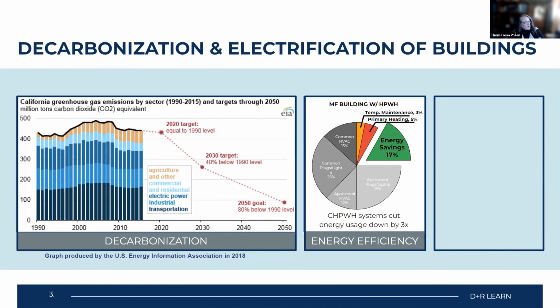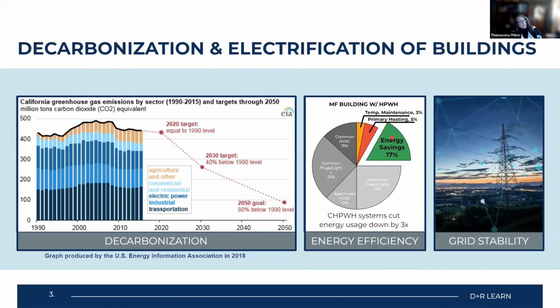Now, if we were to take out an electric resistive load for the water heating and install a heat pump system, then you're cutting that consumption by 17% of the overall consumption of the population. And that's 2/3 of a savings, or you're cutting it by 2/3. Now, the other thing about heat pump water heaters is that they can respond to demand response events. And what that also means is that when the consumption is high and the grid starts to become unstable, the heat pump water heating system shuts down, and you can ride through these demand response events with ease because you've got a lot of storage in those water tanks.